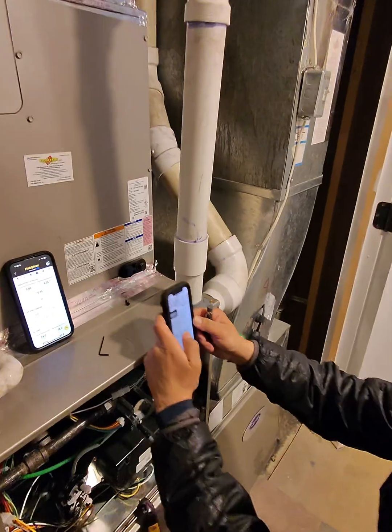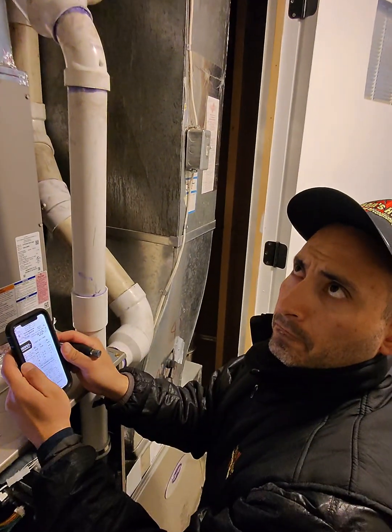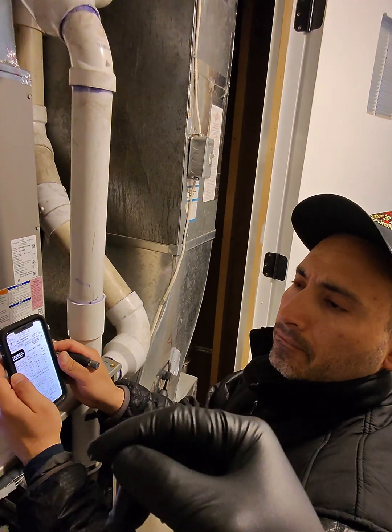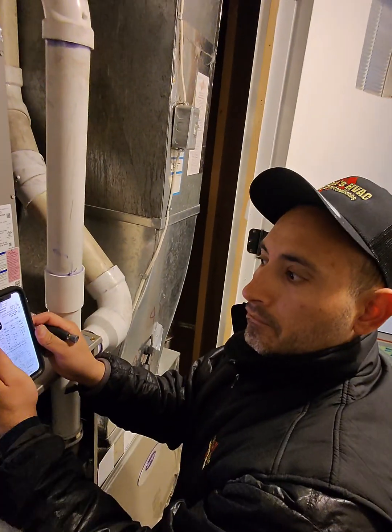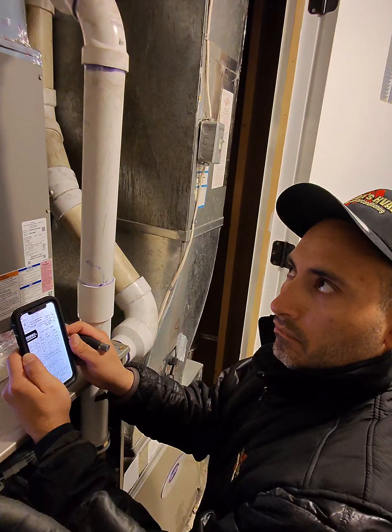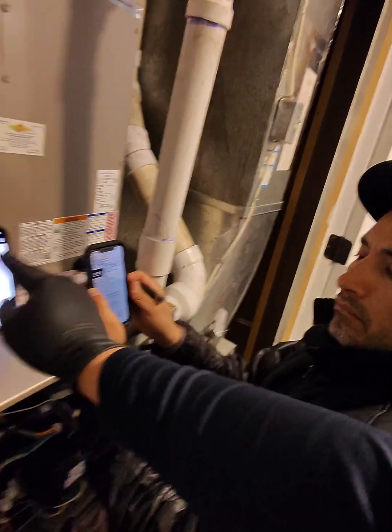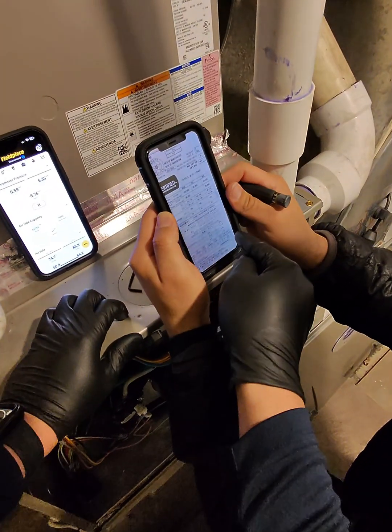Now, what do you think happens to the guy who's quickly changing the gas pressure based on seeing the initial 1.5? They didn't wait until it turned on — the blower motor kicking on and all that. They're changing it when they shouldn't have changed it. They should have waited until this inflection point. So right now we're at 0.60, and then right here we're going to look at the...